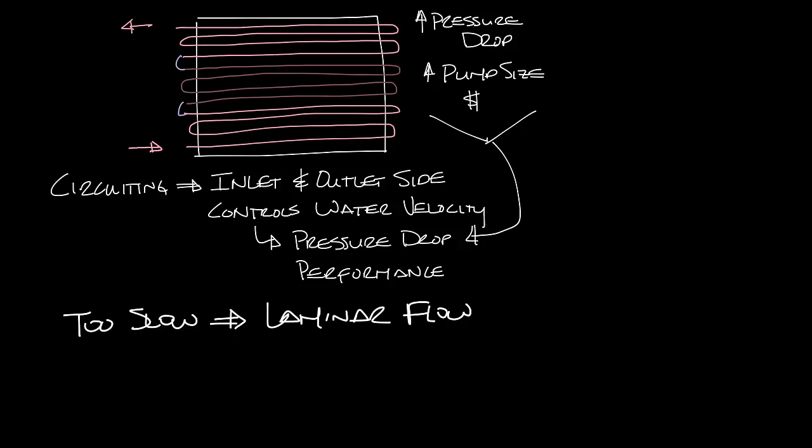This is where all the water is traveling smoothly through the coil and there's no turbulence in the tube. With laminar flow some of the water is traveling in the center of the tube and never touches the tubes to transfer heat, so it reduces your performance.